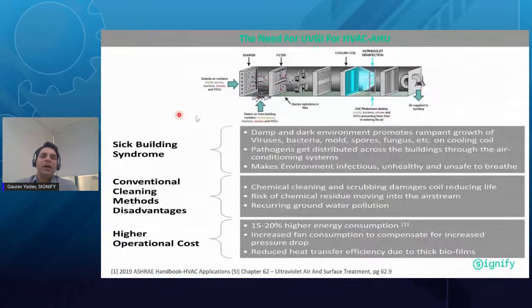So what is the need for a UVGI system to be installed inside the AHU? First, I'll talk about the ultraviolet germicidal irradiation system, which can be installed inside the HVAC system. HVAC stands for heating, ventilation, air conditioning and refrigeration. The need to install UVGI is that we want to avoid sick building syndrome, we want to avoid the conventional cleaning method because there are some disadvantages with it, and we want to avoid higher operational cost. So these are the three reasons why we need to install a UVGI system inside the HVAC.